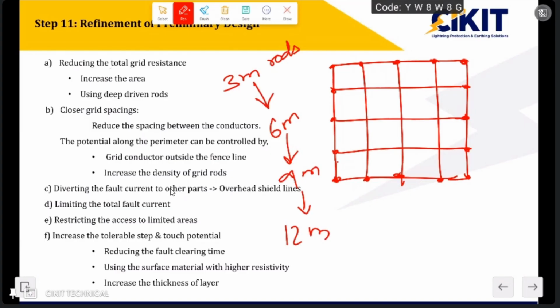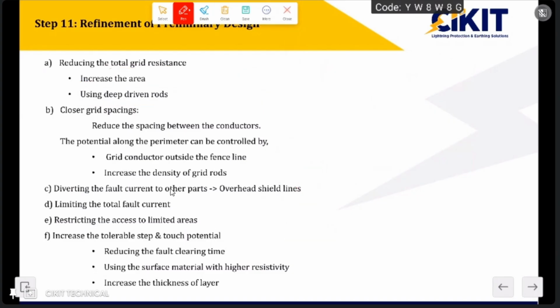So one point for reducing this RG value is to increase the area, and another provision for reducing this resistance value is by using deep driven earth electrodes. We can increase the number of rods, or we can increase the length of the earth electrodes to maintain the step and touch voltages within the limit. The second point is using closer grid spacings. If I'm increasing the area, the number of conductors is increased. Because of this increase in conductors, we are reducing this resistance value.